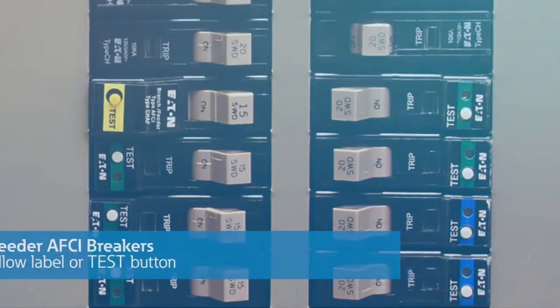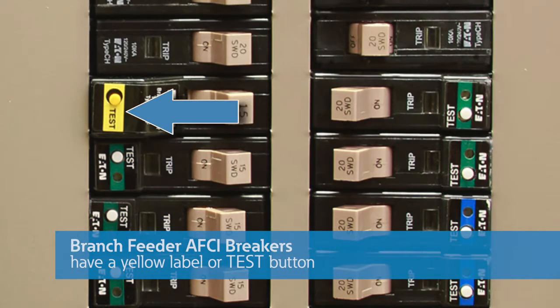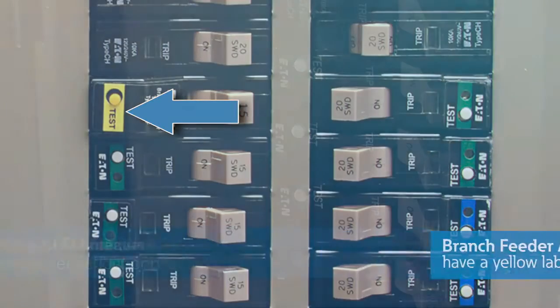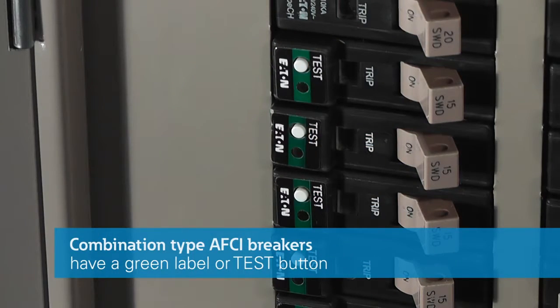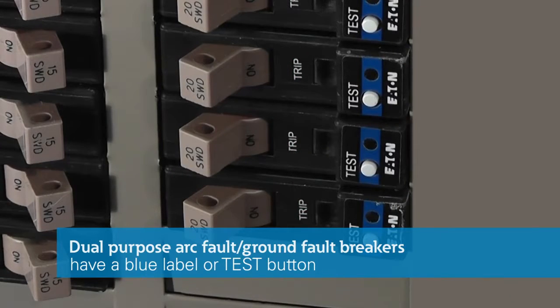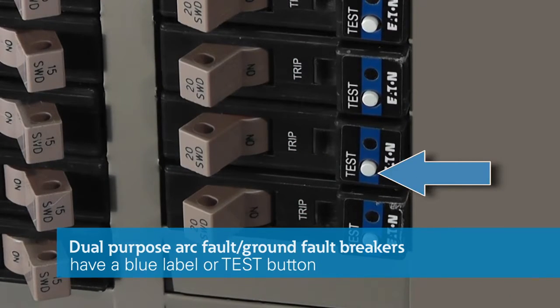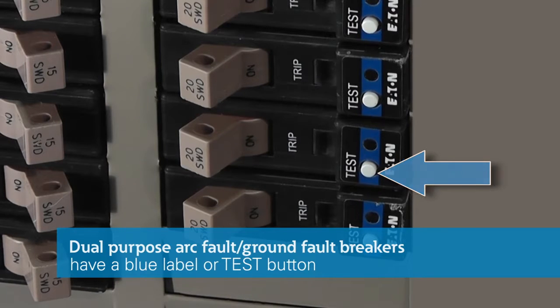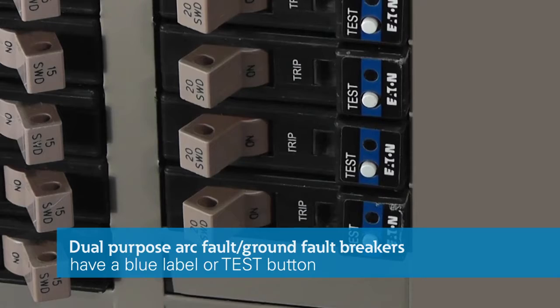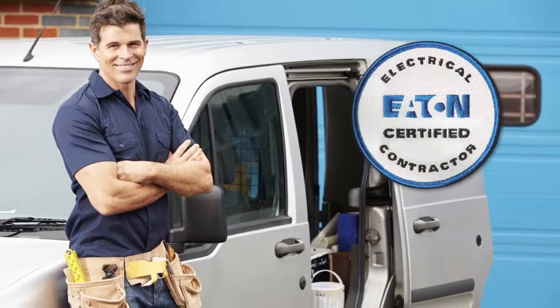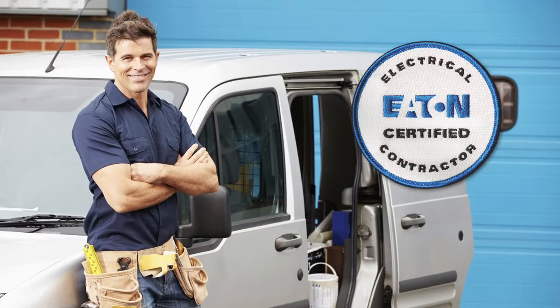Branch feeder AFCI breakers have a yellow label or test button. Combination type AFCI breakers have a green label or test button. Dual-purpose arc fault ground fault breakers have a blue label or test button. These type of breakers include both arc fault and ground fault protection. If you have questions or concerns about your electrical system, have it inspected by a certified home or electrical inspector.